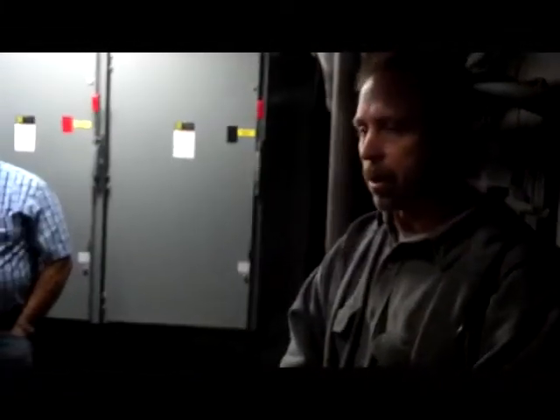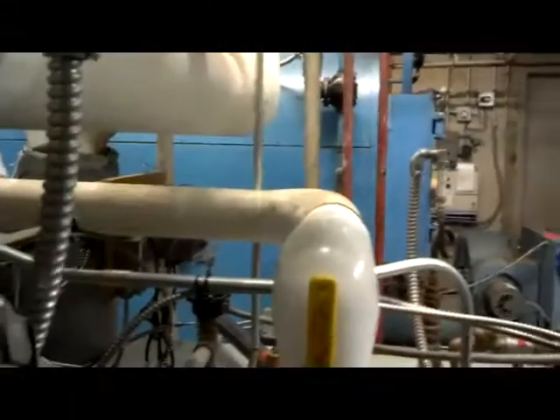You would have fewer chemicals used because you won't be dumping as much. We could possibly tie it into the number of blowdowns. If we can get an output from your conductivity meter, we could display the conductivity on your system through the PLC. That would be just a contact into my PLC. And if you had to, you could override it and go back to the old system by going to local control. So there's a couple of different options.